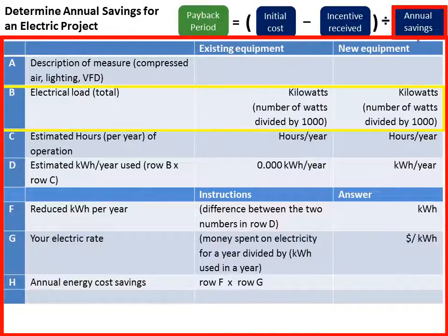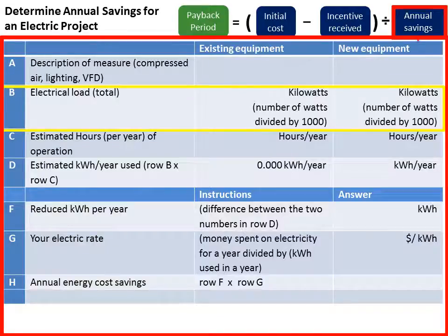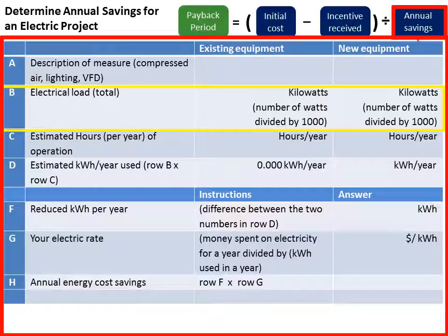To calculate your annual savings, you'll compare the amount you spend on electricity for your existing equipment to the amount you will spend for your new equipment. To do this, first determine your electrical load in kilowatts for the existing and new equipment. You can find the number of watts by looking at the model number on the manufacturer website, or you could also use an average. Then take the number of watts used by the equipment and divide by 1000 to get kilowatts.